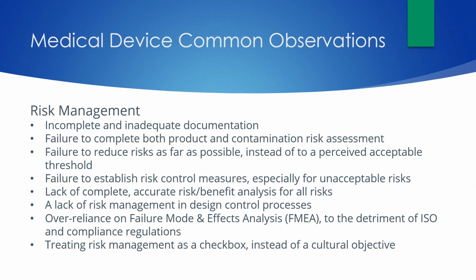Now we're going to discuss some common observations that have been noted recently by regulatory authority in the area of medical devices. The first topic, risk management, is noteworthy because several regulations and standards have been updated to include risk management or update and elaborate on risk management requirements. So several areas have been a theme under the risk management heading, one being incomplete and inadequate documentation. So for example, there was an observation that noted that despite the fact that inadequate product packaging was a life-threatening infection risk, the manufacturer left this field blank on the input-output risk table.